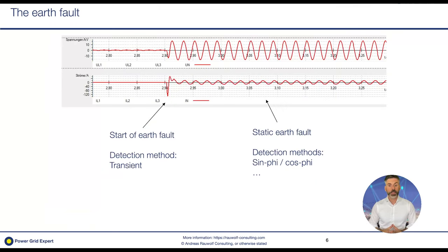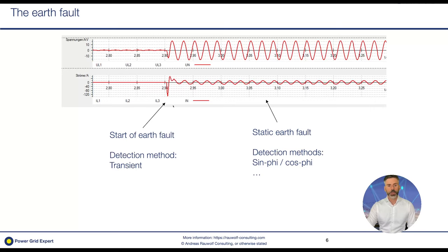Let's have a look at what happens during an earth fault in these networks. We look at the zero sequence voltage and zero sequence current. If there is no fault, these signals are basically zero. When an earth fault happens, this changes dramatically. The transient signal at the beginning is quite high compared to the following static earth fault, but it is also very short — we are talking about a frequency between 100 Hz and 1 kHz typically.